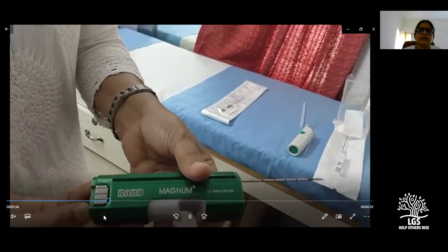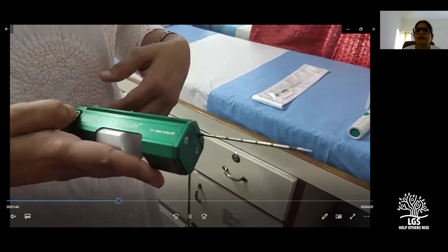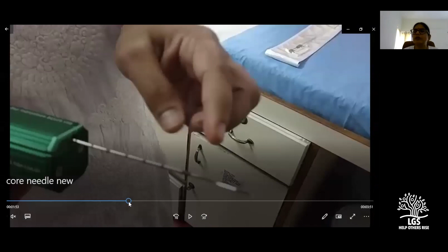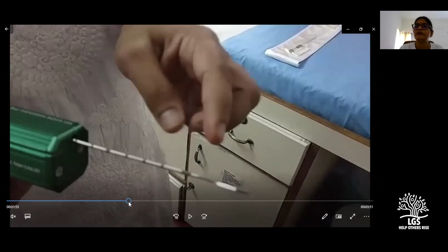This silver button here is the trigger, and the knob that I turned can actually fix the throw. So this is also 9 centimeters. Once you position and fire, this moves forward, and then you pull back once, and you get the sample. On pulling back, you see the cutting chamber here, and you take it out. This pulling back, you have to do in one stroke. I have seen people struggle with it, making 2-3 pull backs, because it's quite stiff, both with that other needle and this.